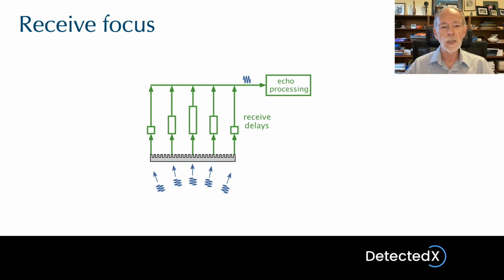You remember that the machine calculates the depth each echo comes from the arrival time of that echo. This means that at any one time, the machine is receiving echoes from just one depth, and the machine knows what that depth is. So the machine is able to calculate the correct received delays, the correct focusing, for the depth at which the echoes are coming from, and to then adjust that moment by moment so that it is always correctly focused while it's receiving. We refer to this as dynamic focusing.